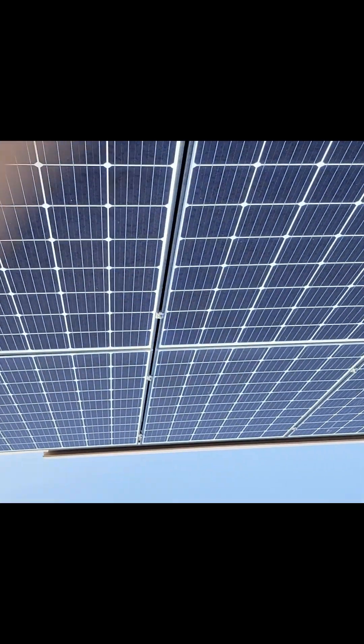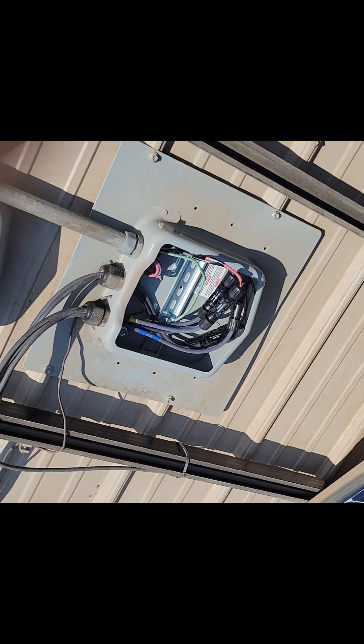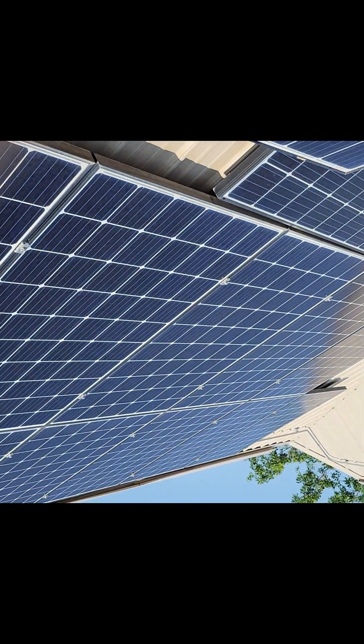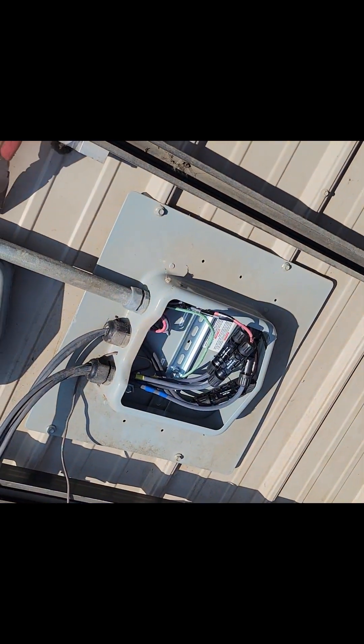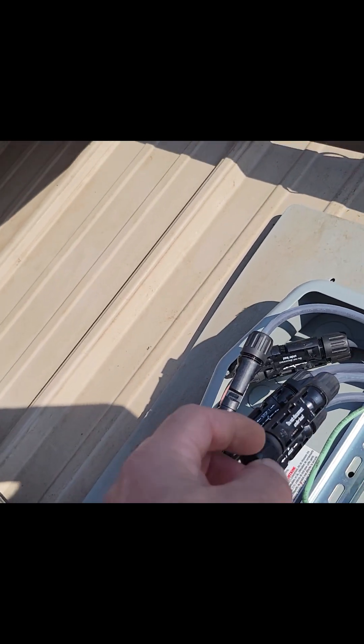If I'm changing just the inverter and not changing anything else, does this system need rapid shutdown? We've been doing it without putting rapid shutdown in. Talked to a few inspectors around here and they say it's fine. I'm curious to see what others around the country would think about that. Getting ready to unplug - we got red to yellow one, black to yellow two.